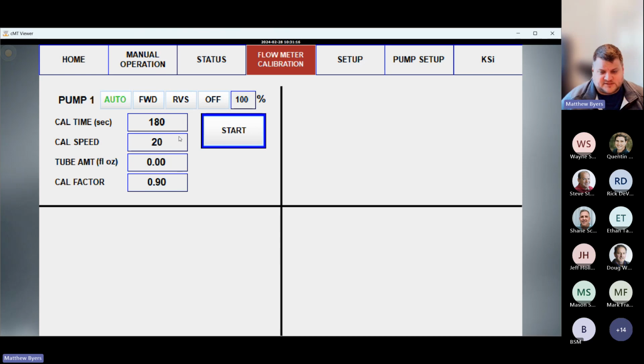It will run at 20% for 3 minutes. You will come in and type the amount of ounces you see in the tube into this box, and then calculate will pop up under the start button. You just hit calculate and you'll get a cal factor. Again, as we talked about last year, that cal factor should typically be anywhere from 0.95 to 1.1. If you start getting cal factors outside of that range, that's usually a pretty good indication that the flow meter is getting gummed up or dirty and just needs cleaned. So go ahead and review that and calibrate those.